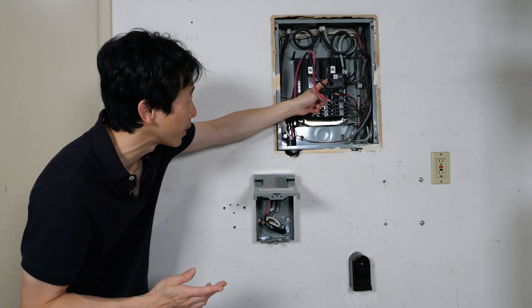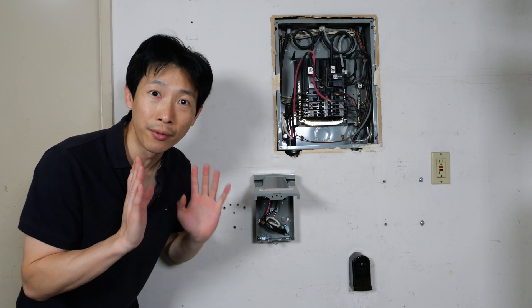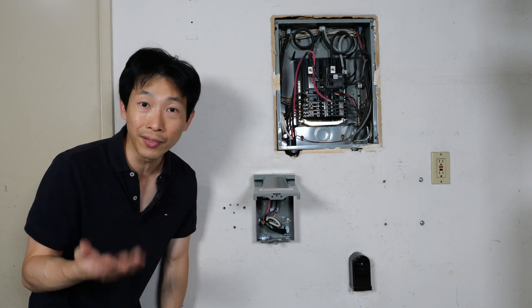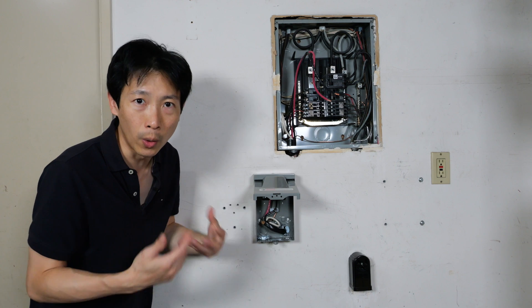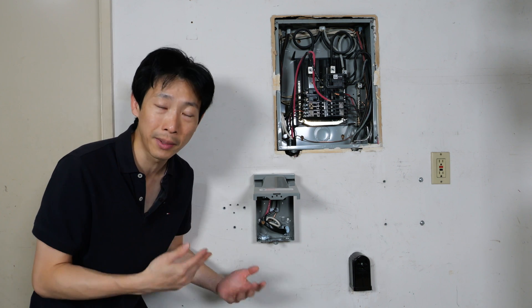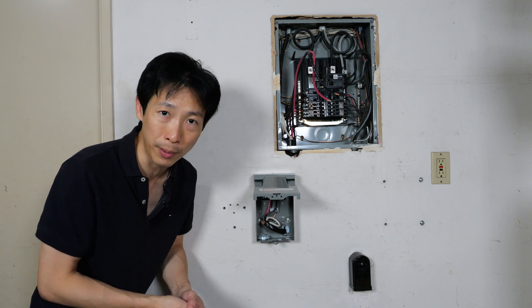I used to have a 50 amp breaker here and it can charge up to 40 amps. So when you go up to 50 amps, you get that 25% more. The 50 amp breaker won't support a 50 amp charger because if it charges at maximum, it will trip the breaker.